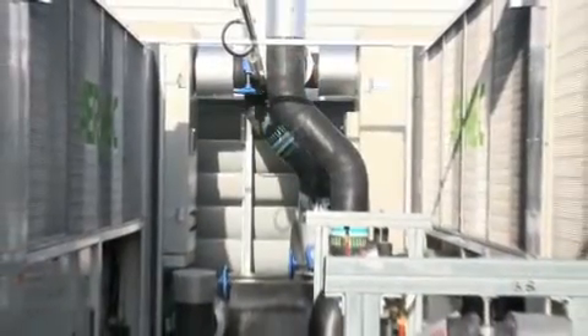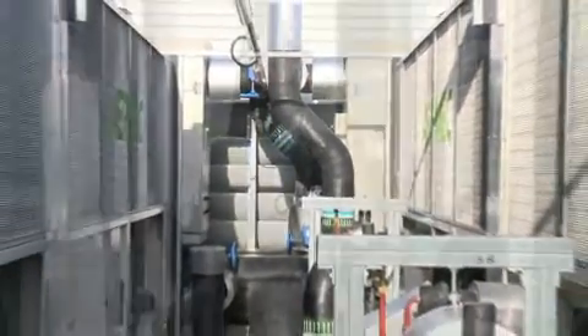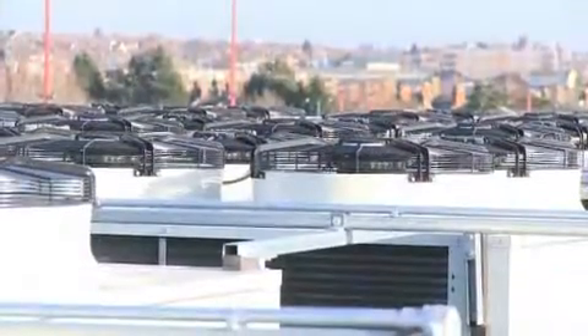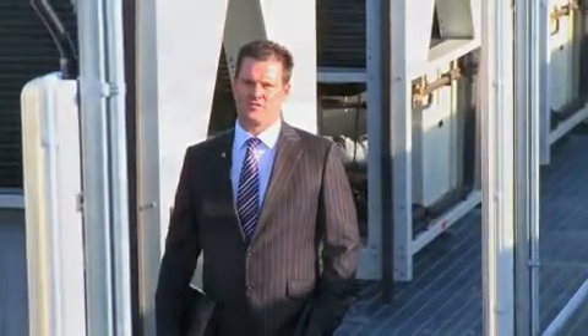So we have 12 1.2 megawatt dry air coolers. These units are the units that extract the heat from the cooling systems within the data halls. Should one of these units fail, they're all set up on an N+1 basis. We also have the additional benefit of free cooling if the external temperature drops below 10 degrees.